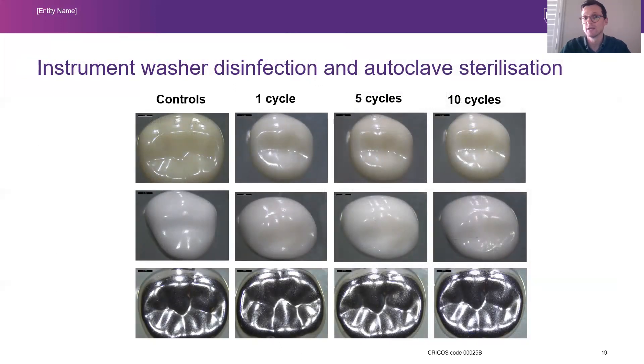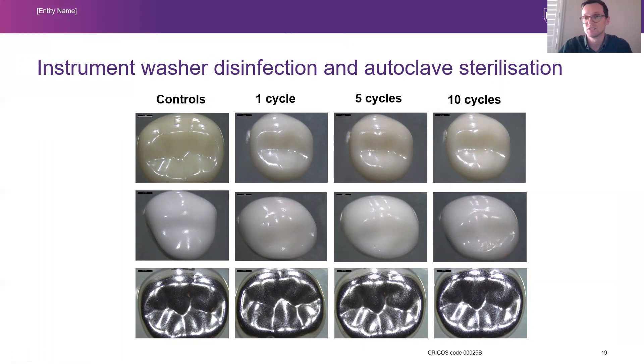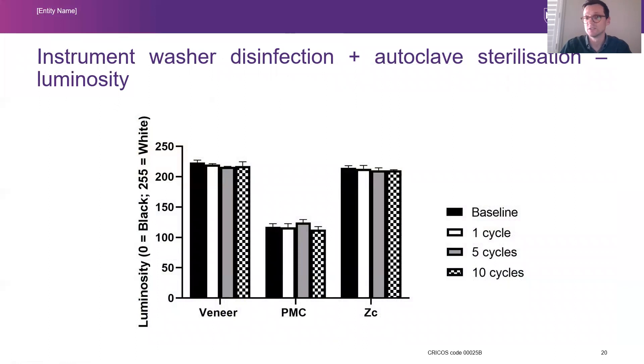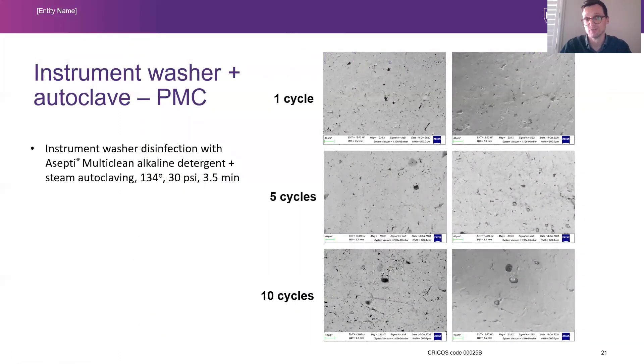For the instrument washer group at one, five, and ten cycles, we did notice for the veneered crown material that we were getting a chipping or fragmentation of that veneer layer. The underlying stainless steel layer is starting to peek through in a few regions, and that was noted mostly towards the end at eight, nine, and ten cycles. For the zirconia and the preformed metal crown, no differences were noted. Luminosity levels showed no statistical differences from one through to ten cycles for the instrument washer disinfection and autoclave sterilisation, and for the preformed metal crown SEM images, no differences were noted.